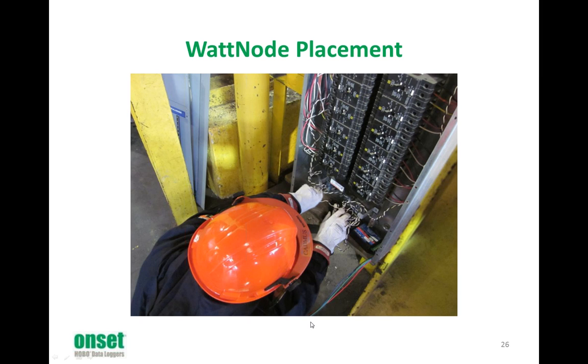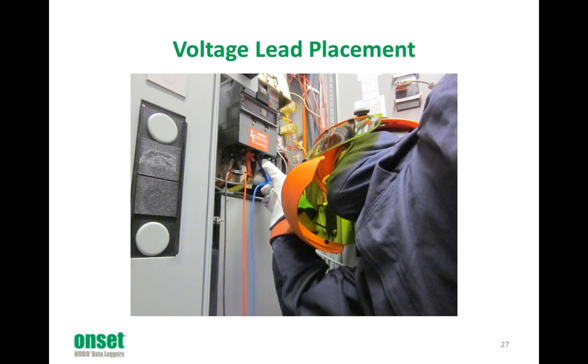Okay, now we're getting into Wattnode placement. It's important that once we get into the panel and identify the voltage, we look at a safe location to place the Wattnode. We'll then do voltage lead placement. So take an idea at where you're going to tap the voltages. Again, in most cases, it's going to be 3-phase, so you're going to have a black, red, and blue voltage lead going to the Wattnode.